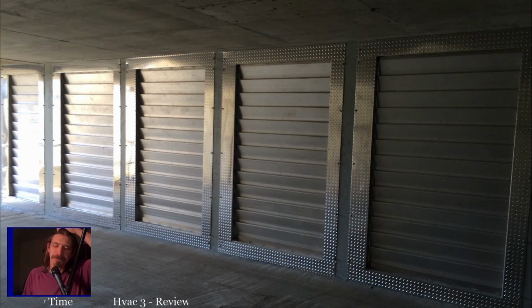But anyway, I don't know how many times I've heard somebody talk about changing out a thermostat and still having the same problem they had before. I can count that on more hands than I need to count how many times I've actually run across a failed thermostat. It does happen. Don't rule it out. But assume it's probably not the thermostat, and you should probably be checking everything else first, which again is why I don't jump wires at the thermostat often. Generally, if a wire's broken, I can figure it out by the way the voltage behaves, and it's pretty rare that you actually have an issue at a thermostat.